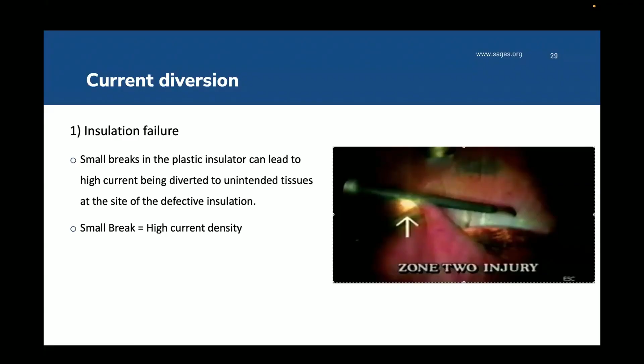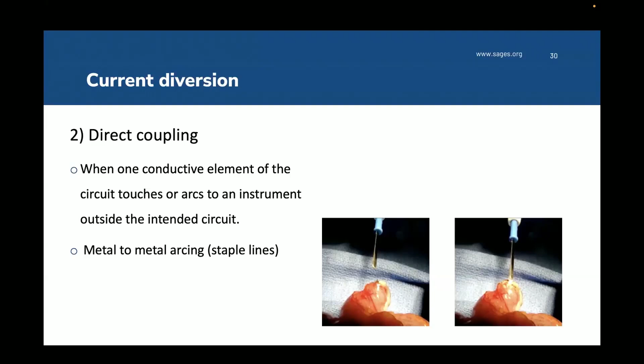Direct coupling. We do this on purpose when we grab something with a debakey and deliver current through it. But it can also happen accidentally when the current sparks to unintended tissue and leads to injury. One example of this is metal-to-metal arcing, such as when delivering energy close to metallic clips on a staple line. These clips are small, and they'll focus your current in a very small area, leading to the temperature in the adjacent tissue rising very fast and potentially causing staple line leaks.